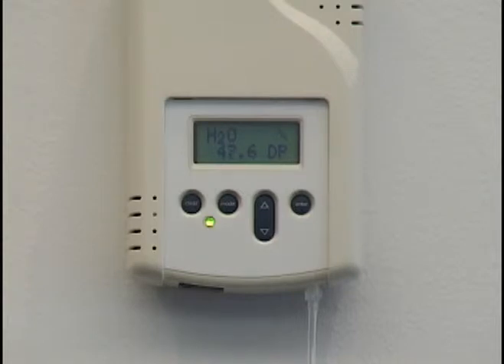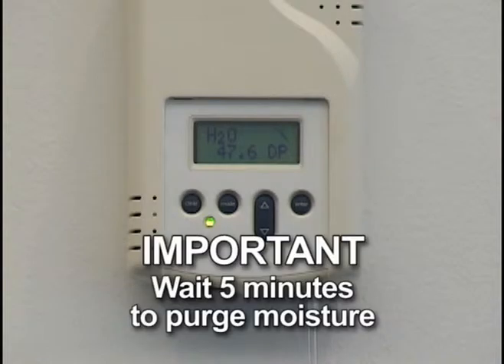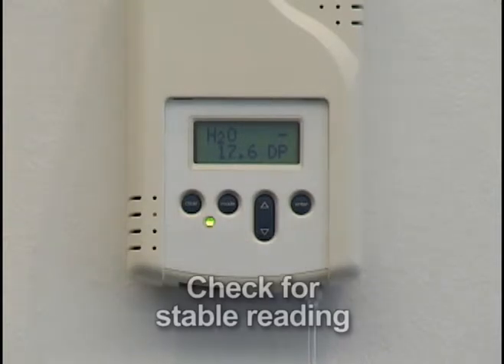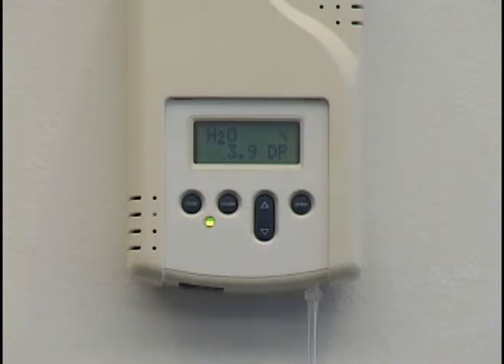With gas flowing, wait 5 minutes before proceeding. This waiting period allows the gas delivery to purge any moisture from the calibration kit and sensor to ensure an accurate calibration. This waiting period is important and cannot be cut short. Look at the VaporStat display and monitor the reading to verify it has stabilized. If the reading is still dropping, continue flowing gas until the reading stabilizes. If the reading stabilizes at 12 degrees Fahrenheit or lower, continue calibration. If it stabilizes above 12 degrees, the sensor should be replaced.